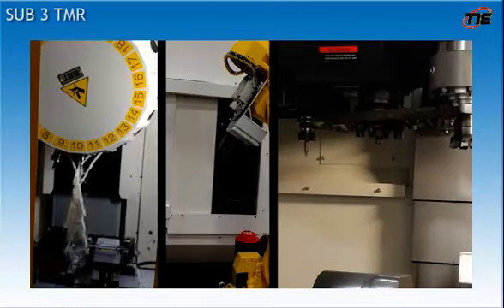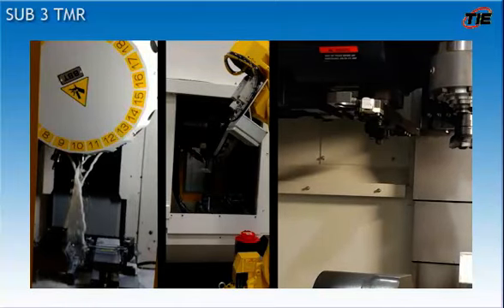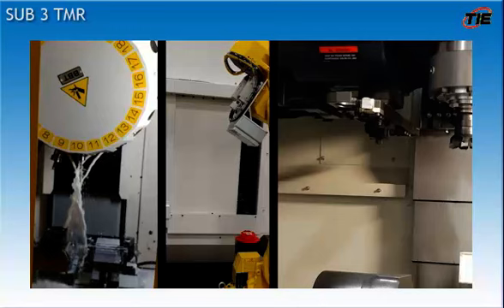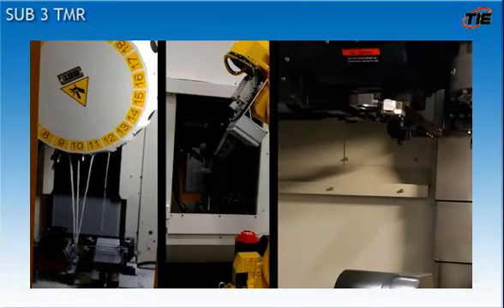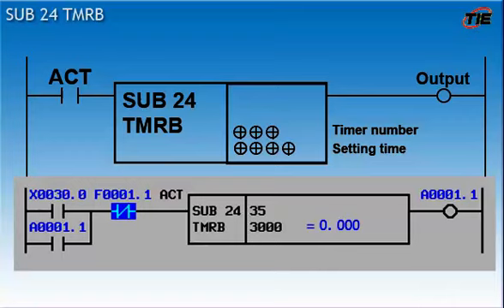Variable timers can be used for items such as lube pump on and off time, indexer rotation overtime, door open, close overtime, or other functions. The Sub 24 function is known as a TMRB timer. This is a fixed timer. This means that you can't modify the timer value.